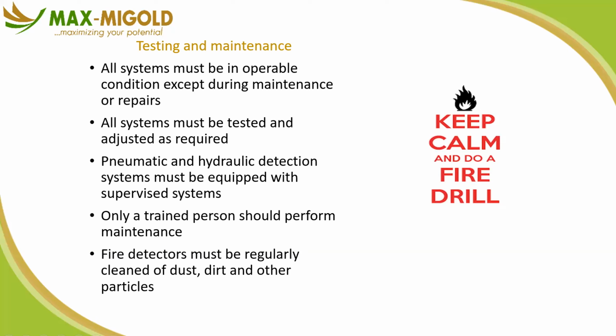There could be need for operational upgrade, repair, or maintenance. Yes, it's allowed, but depending on the facility. For instance, when I was in downstream oil and gas, if you want to carry out critical fire equipment intervention, we have a fire truck on standby with firemen. Those are good practices, having people on standby, because when you disable something around the fire pump, even though it's still functional but not working optimally, and you decide to go and start work, fire might choose that very day.